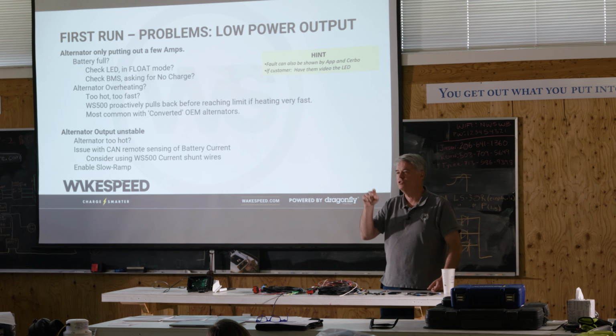If that's happening, you'll see cycling going on, and again the log file will tell you, because you'll see a target value for the amps, but you'll see the amps going significantly over it and then getting cut back. It's just that we're not getting enough responsiveness.